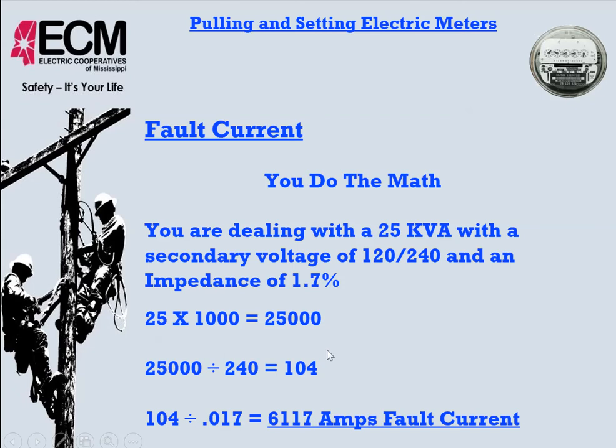To get the fault current, we divide by the percentage of impedance, which would be 0.017. If you do that math, it comes out to be 6,117 amps of fault current. Now, a lot of our primary lines don't have that much.